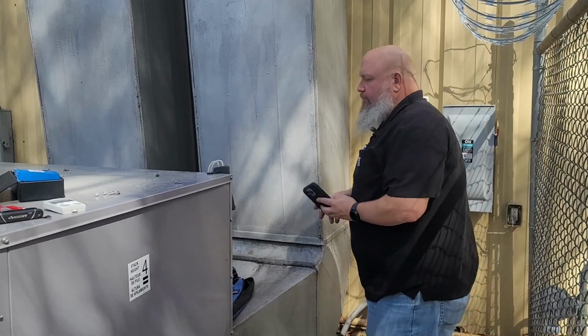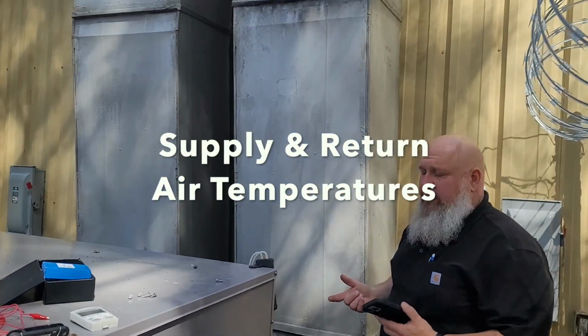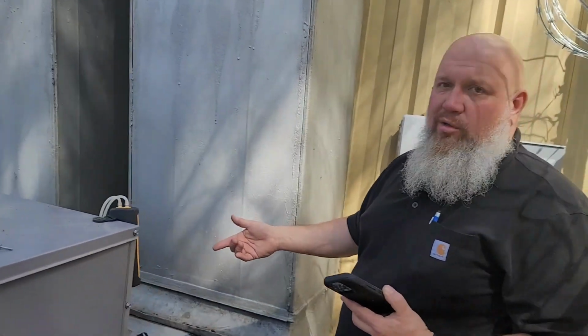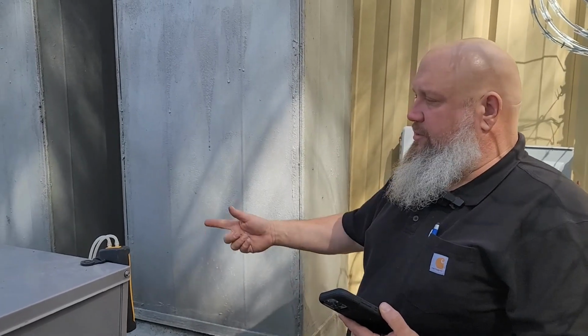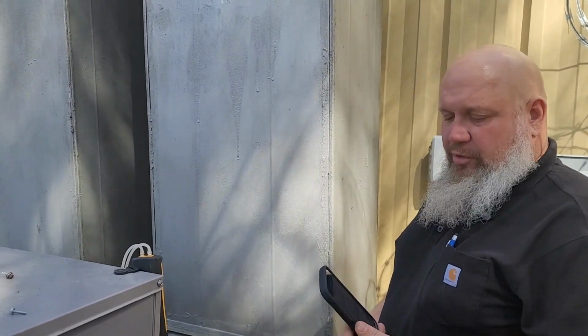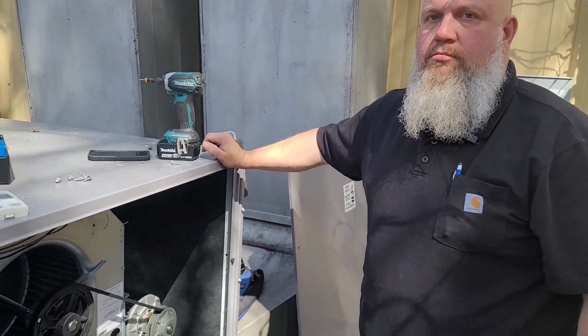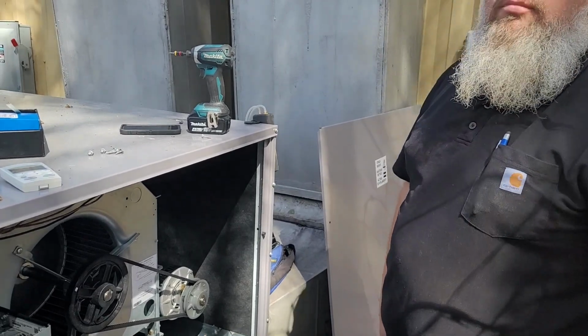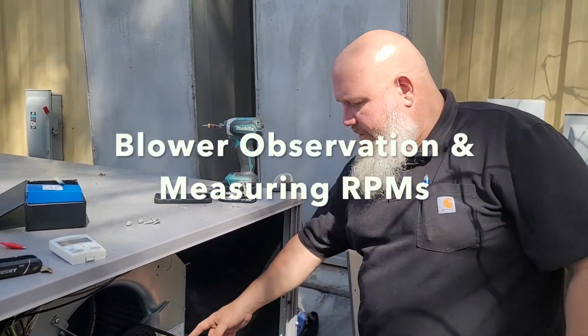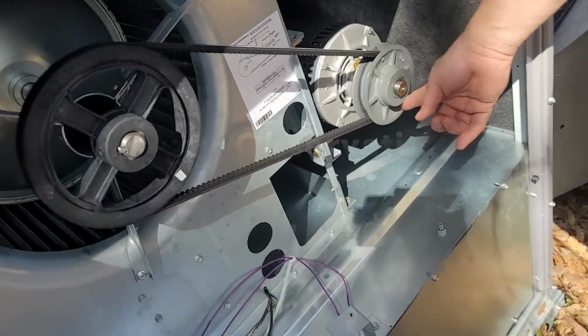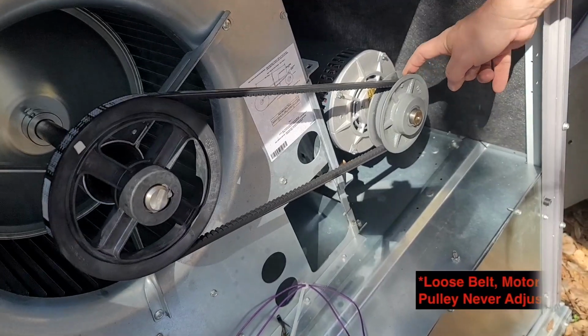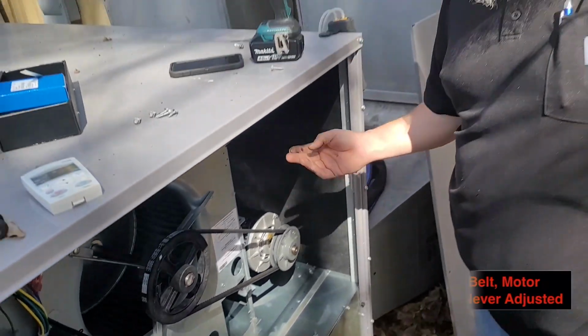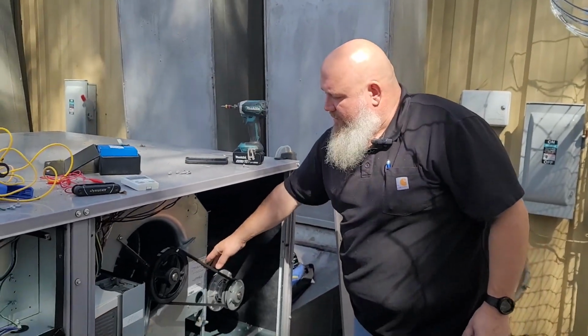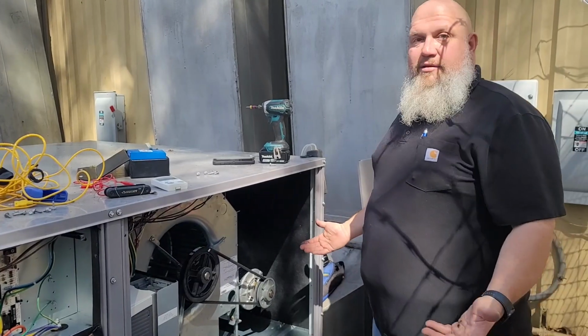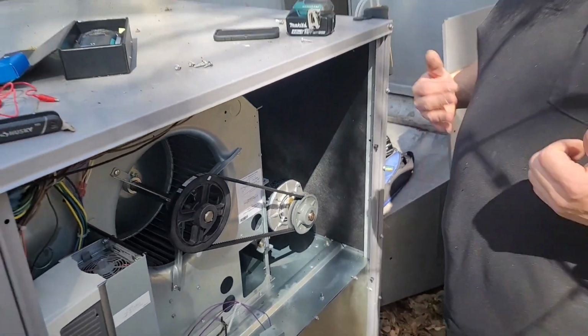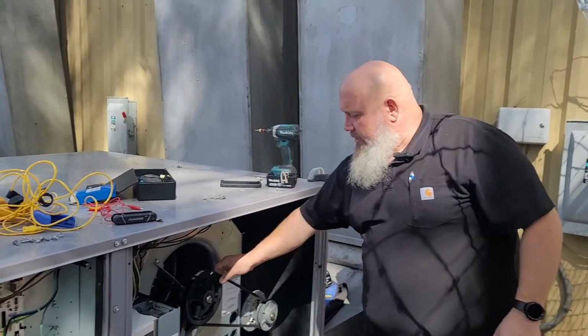Okay, what are we doing? What are we inputting at this point? We're doing the supply and return air temperature. So using the same holes, you use your probe to check your temperatures, let it sit for a couple minutes, and input your information. So we're now dealing with the blower section. Tell us what your observations are and what measurement you're about to perform. Okay. The first thing I notice is the motor pulley is still in the factory position, and this unit's been running, and the belt's already wearing out. It's a brand new unit, so we've got to make sure we've got the blower set up properly. So that's telling me that it's possible that we need to adjust this motor to spin this just right.